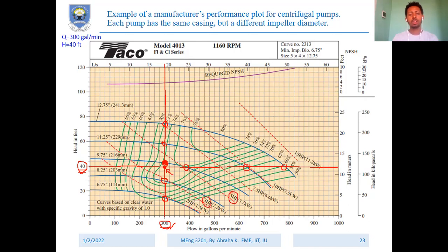So approximately, if you consider this by scaling, by partitioning the points, we may get it around 4.5. If you divide this line exactly at the mid, we may get 4. Now the point is between 4 and 5 horsepower, and if we further divide this at the center, it becomes 4.5.